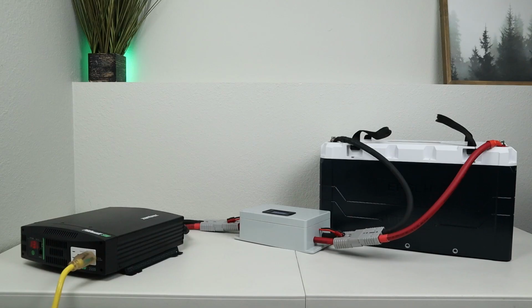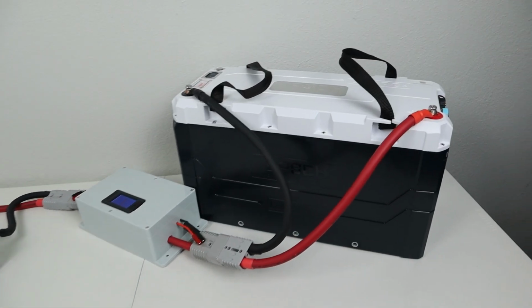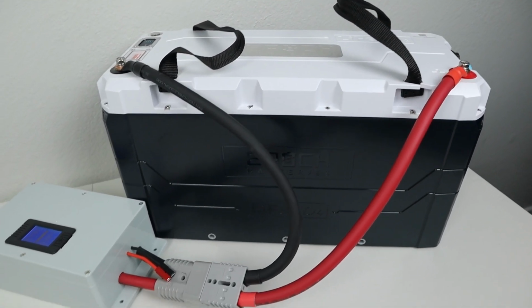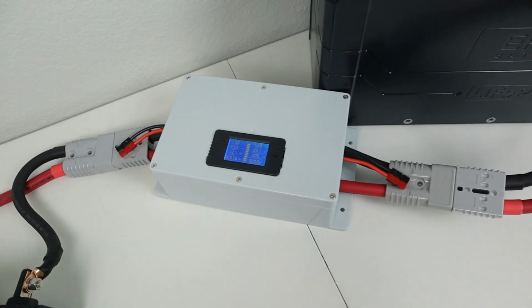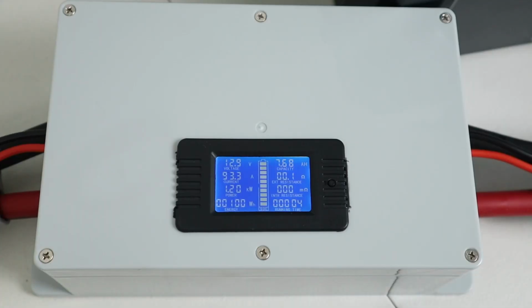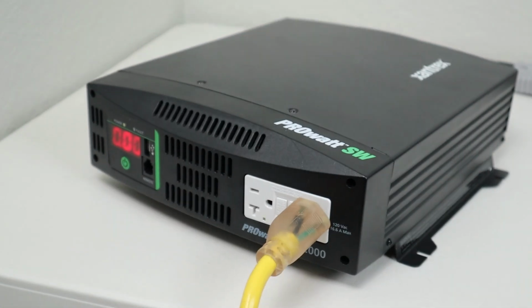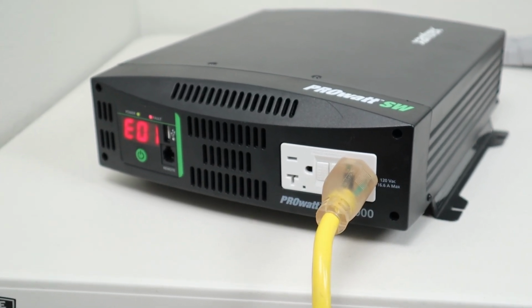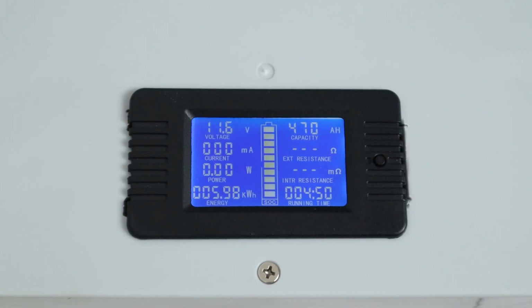The first test I wanted to do on this battery was a complete discharge test to see if we could pull the full rated capacity of 460 amp hours. As I started the test, I tracked all the power coming out using this inline shunt. I was discharging at a 0.2C rate, and after about 4 hours and 50 minutes the battery was dying, and we pulled a total of 470 amp hours, or 5,980 watt hours. So we did pull over capacity while discharging this battery.